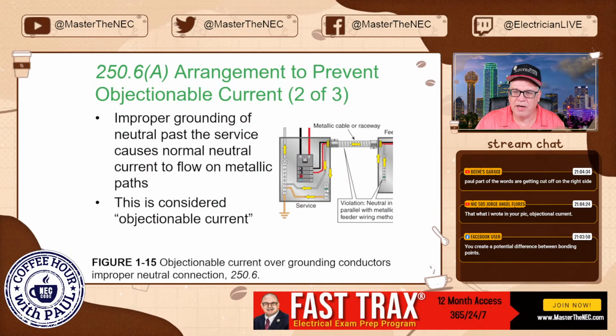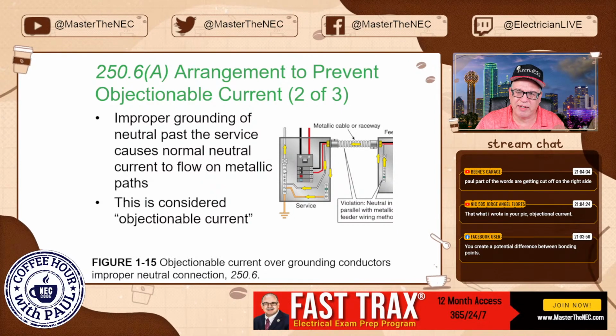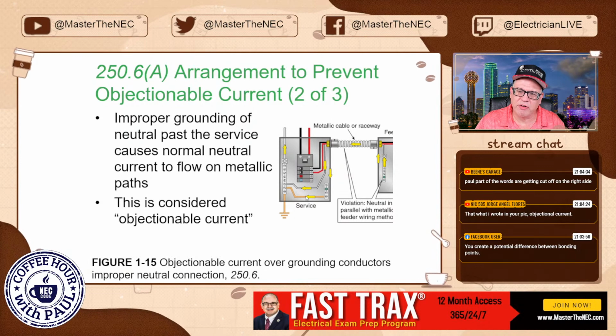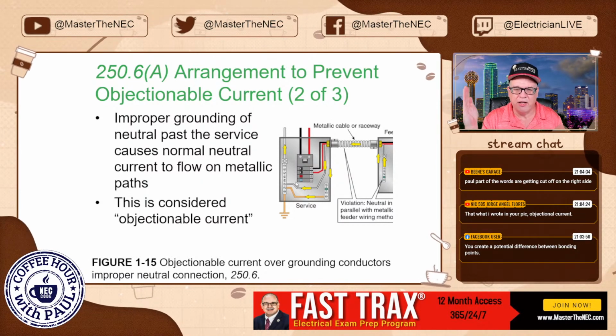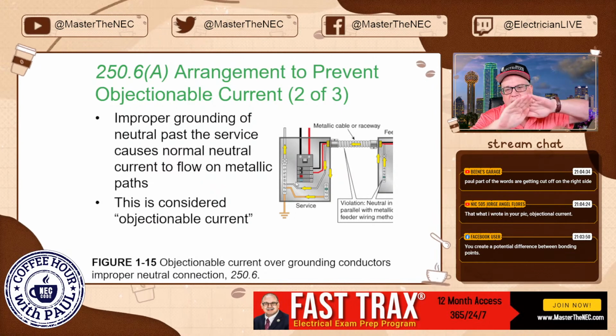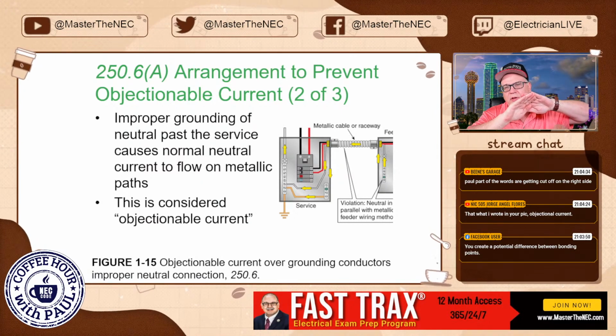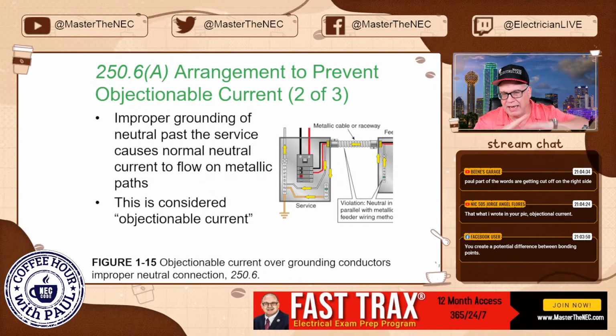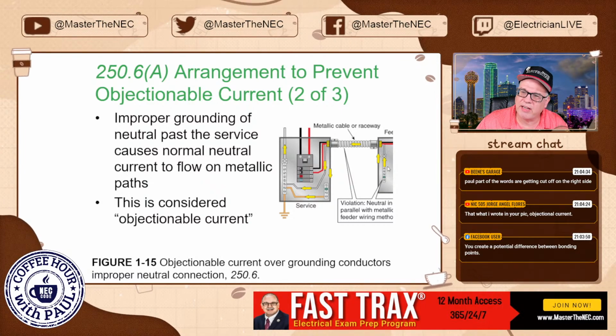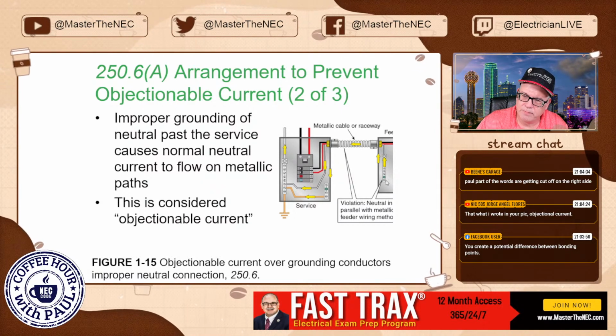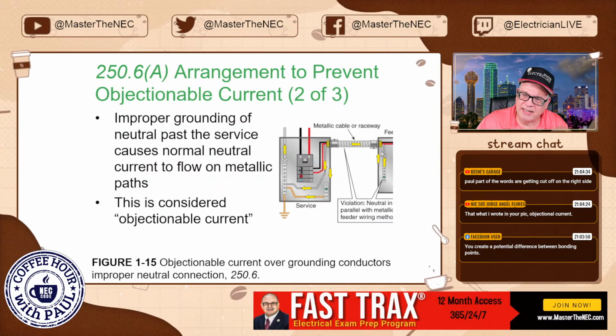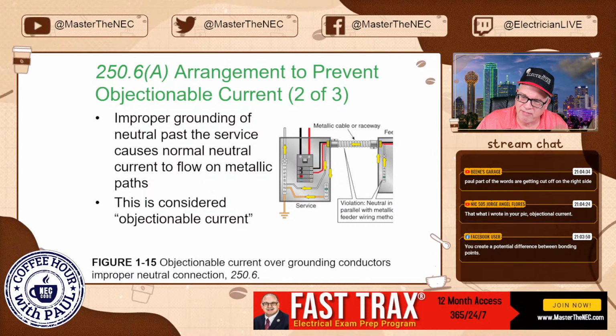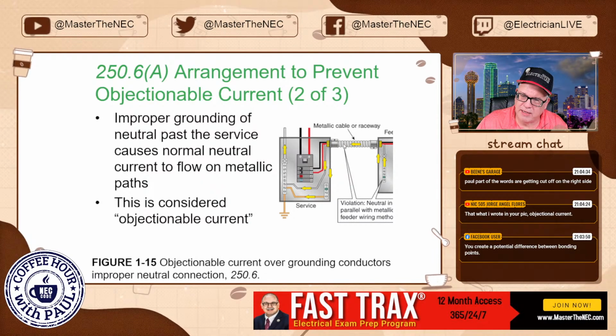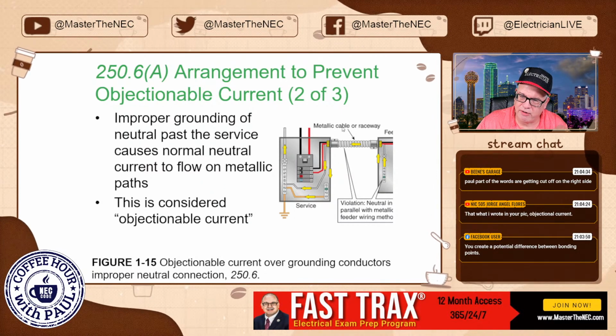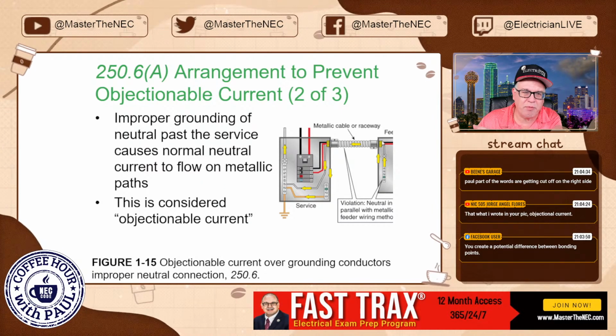Okay. And now, again, remember, this could all be on one bus, and this green screw could have been over here, but Phil likes to separate them so that you understand that the main bonding jumper is used to connect the equipment grounds to the grounded conductor, all to the grounding electrode system in the service. That's why he likes to do it like that. All right. So here's a case. Check this out. This is a remote distribution panel. And here's your bus. And notice here, the green screw is in it, connecting this neutral to the enclosure. Now we have a separate bus because this raceway is being used, right? And this metal is connected here to here.